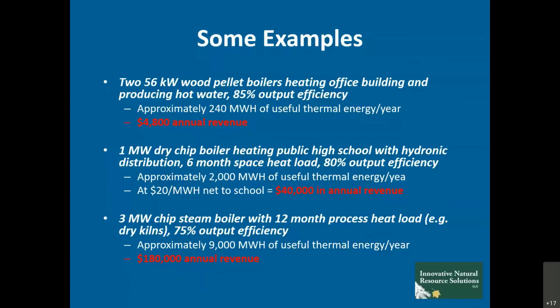Bigger systems: a 3 megawatt chip steam boiler with a 12-month process heat load - maybe dry kilns, food processing, or a big brewery. At 75% output efficiency, that's roughly 9,000 megawatt hours of useful thermal energy a year, and gross revenues of $180,000 a year. So we are not talking pocket change here - this is a very significant incentive.